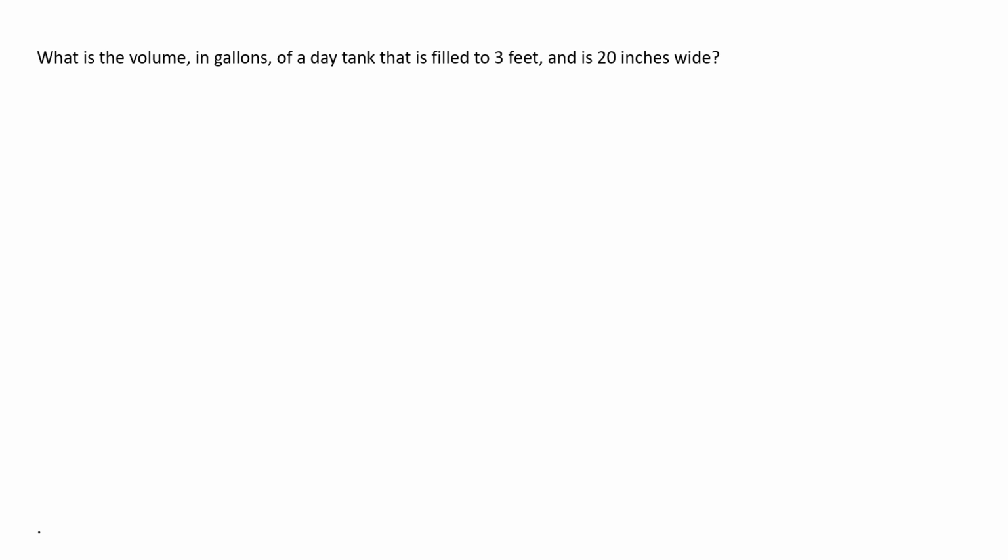What is the volume in gallons of a day tank that is filled to 3 feet and is 20 inches wide? Still pulling out our knowns and unknowns from word problems, because that's what we do around here. What you know is the depth of 3 feet, and the tank is 20 inches wide. If you remember from the diagram and what we talked about there, width is equal to the diameter, because the diameter is the distance across the circle passing through the center. So we're going to be using the diameter formula. And that is 0.785 times the diameter squared times height.